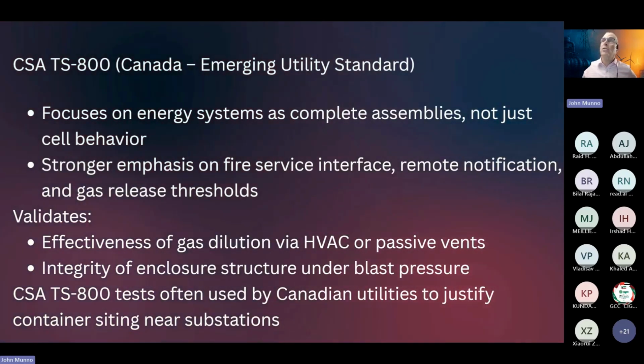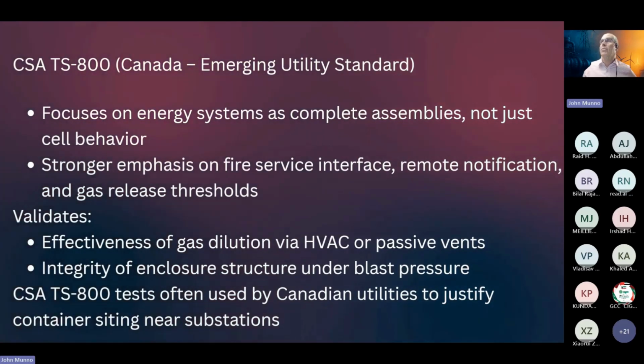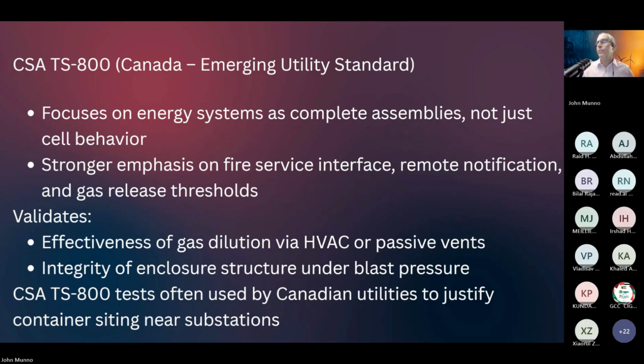And the CSA is Canadian based. It focuses on energy systems as complete assemblies, not just cell behavior. And there's a big emphasis on fire service interface. We haven't talked much yet about how a fire service deals with a battery storage fire. The best thing, and this is from listening to fire chiefs that have responded to many of these, is to not actively try to extinguish the battery fire, but to basically monitor the plume, protect exposures, and try to prevent the spread of the fire from one module to the other. They're not trying to extinguish this fire. They've already realized that that's probably not going to happen. It's going to burn itself out when it's out of fuel.